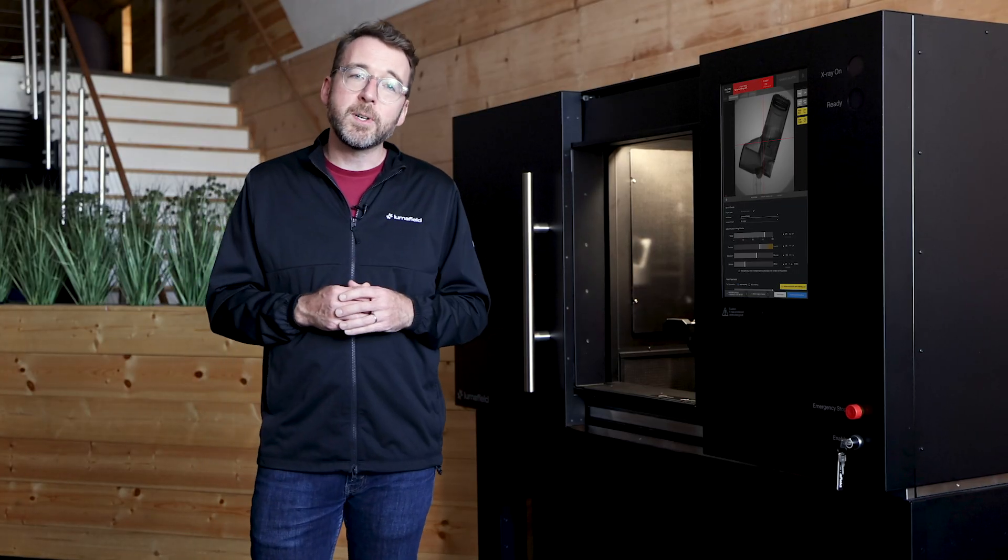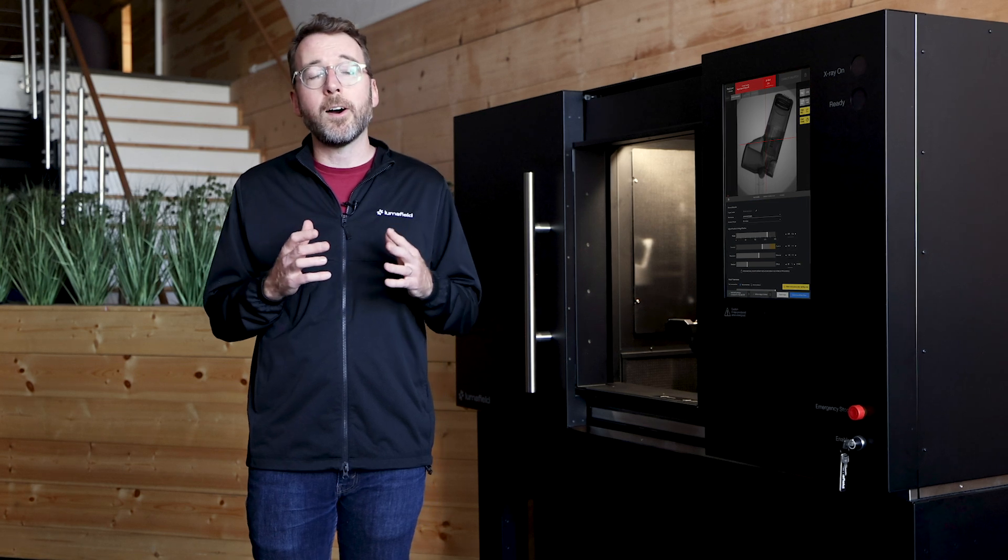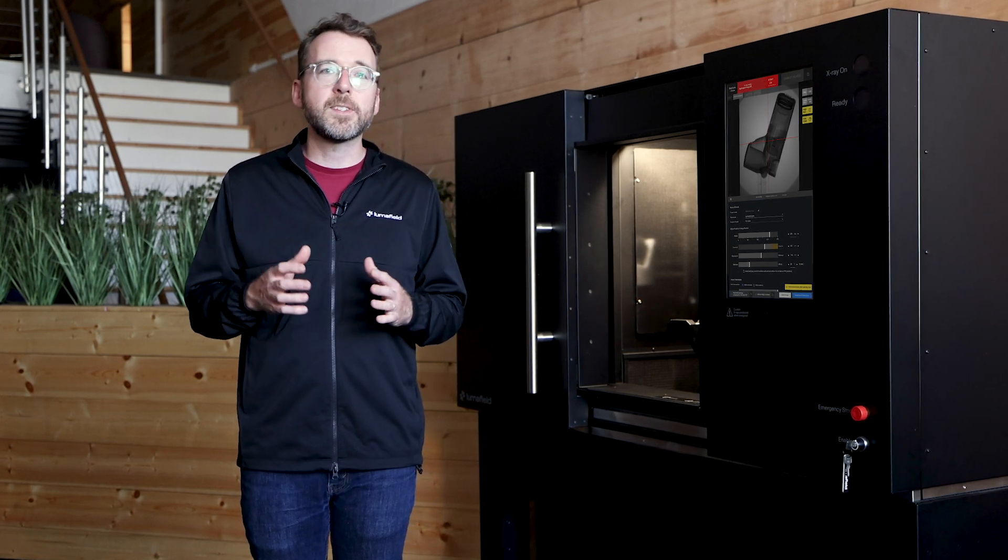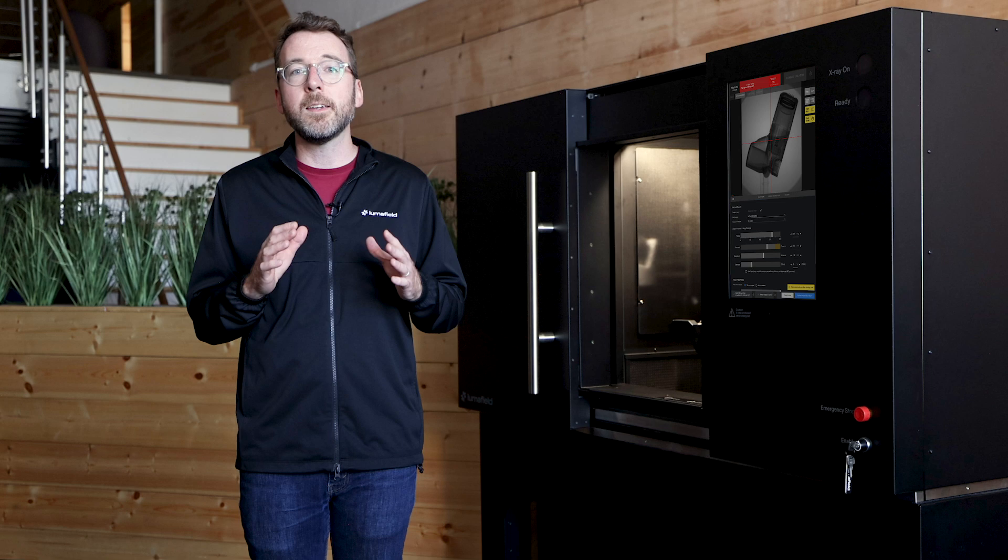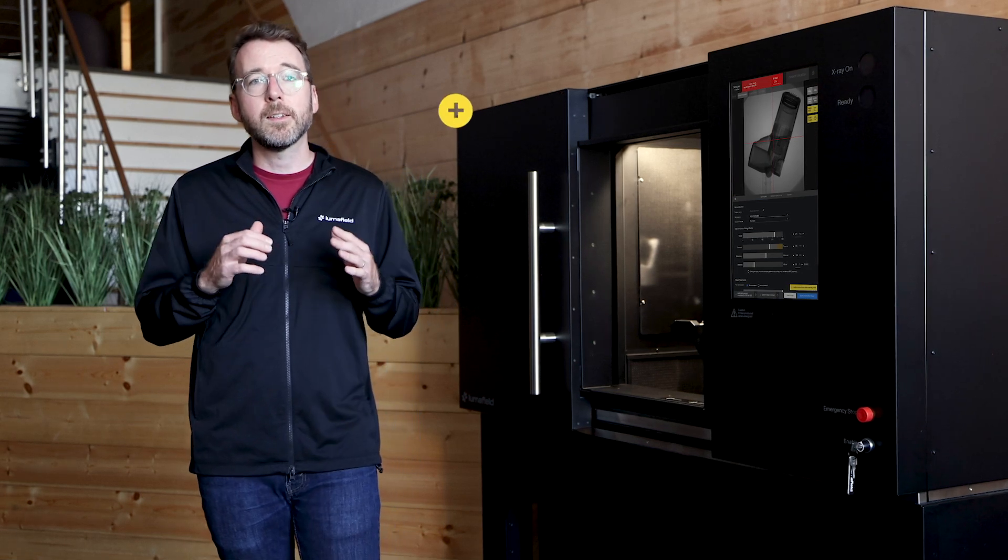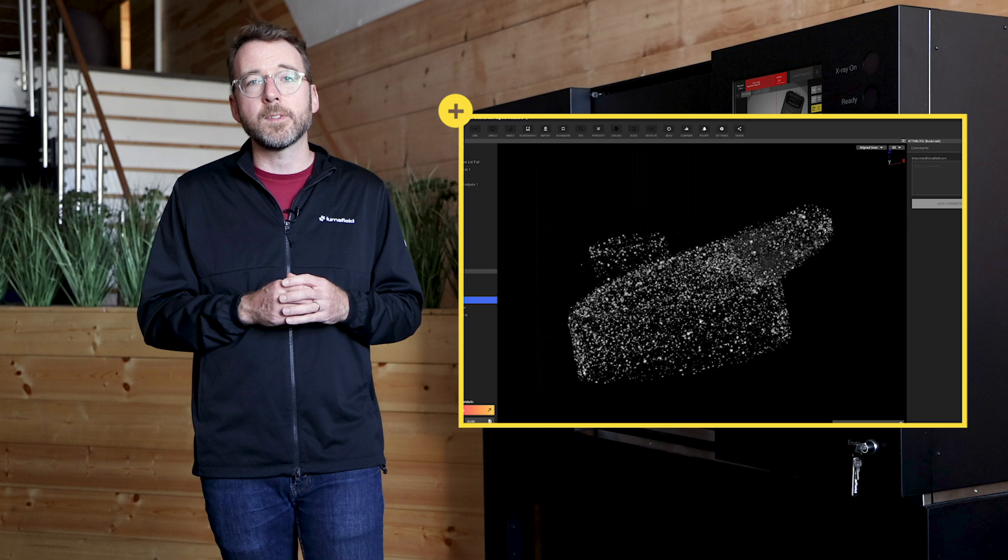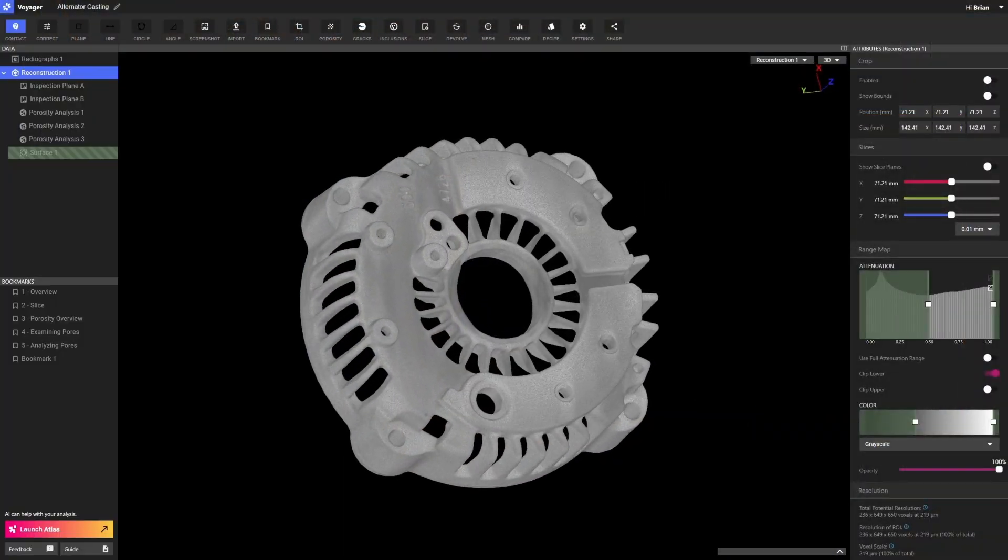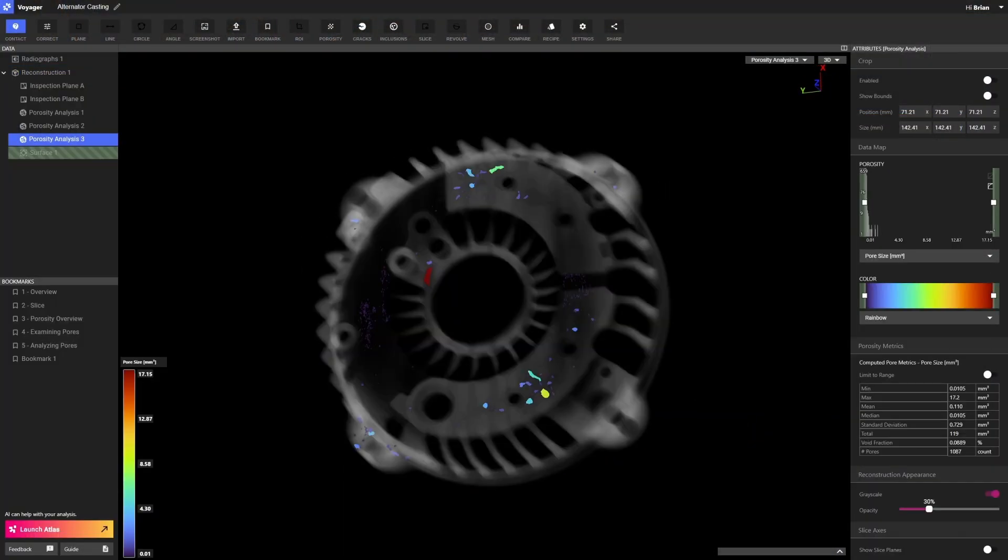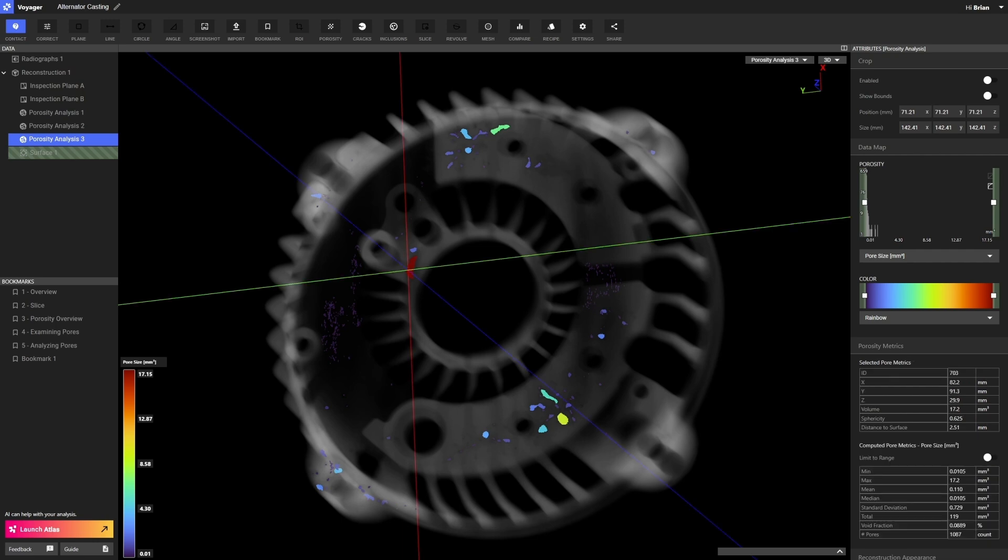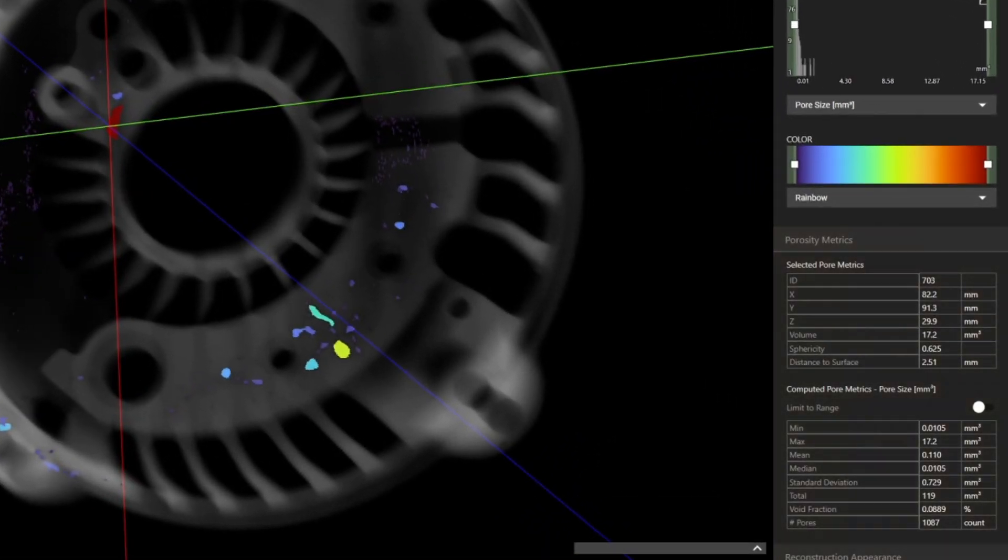Industrial CT is particularly powerful when it's paired with automated analysis tools. For instance, LumaField Voyager can automatically find and measure features like pores, voids, cracks, and inclusions in parts. These can be visualized to quickly identify problems with manufacturing processes, and they can also be quantified, so you can set acceptance criteria based on CT data.